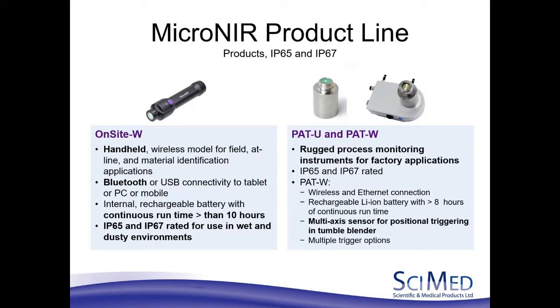We represent Viavi and the MicroNIR range of NIR spectrometers. This generally consists of three main products, the first being the On-site W, a handheld device. This is ideal for in-field, at-line or offline measurements, and it's very well suited to material identification. It's a Bluetooth device, also able to connect to a PC, laptop or tablet using USB, and it's built in with a 10-hour battery. You tend to find the device it's connected to runs out of battery before the NIR itself does.